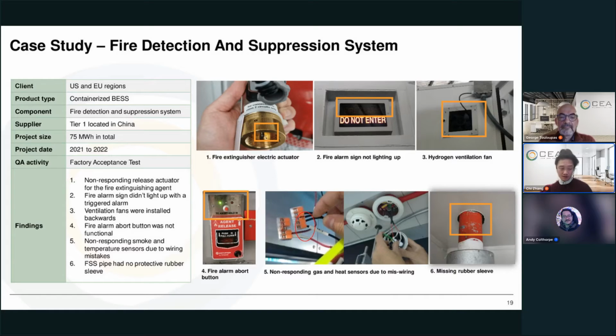Let's take a look at these problems. We have a non-responding solenoid actuator that's responsible for releasing the fire extinguishing agent. We have a fire alarm sign that fails to light up. We also see the ventilation fan spinning backwards due to a miswiring problem. This can be really dangerous, because instead of putting the concentrated hydrocarbon gases out of the container, we are essentially sucking oxygen into the container, creating a perfect stage for explosion.